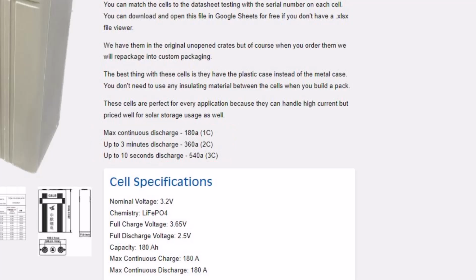And notice that the number next to it has a C next to it, like 1C, 3C, 5C, you might see 10C. That rating is called a C rating. So the continuous discharge rating tells us we can pull 180 amps out of that cell continuously without hurting it. 1C means it's a multiplier of the amp hour capacity. So 1C is 1 times 180 amp hours, which means 180 amps. So at a 3-minute discharge, if it can handle 2C, that means you can do 360 amps for up to 3 minutes before you hurt the battery.